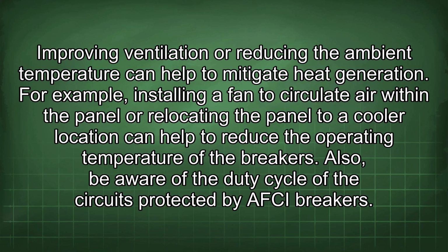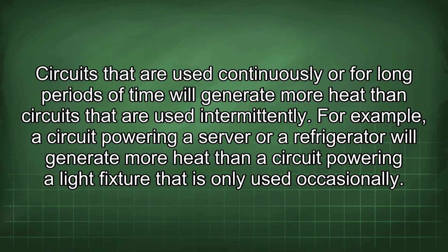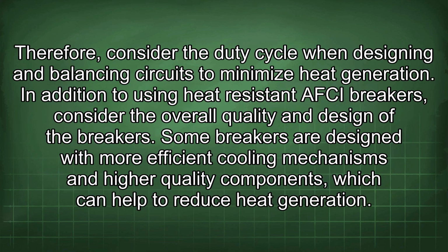Also, be aware of the duty cycle of the circuits protected by AFCI breakers. Circuits that are used continuously or for long periods of time will generate more heat than circuits that are used intermittently. For example, a circuit powering a server or a refrigerator will generate more heat than a circuit powering a light fixture that is only used occasionally. Therefore, consider the duty cycle when designing and balancing circuits to minimize heat generation.